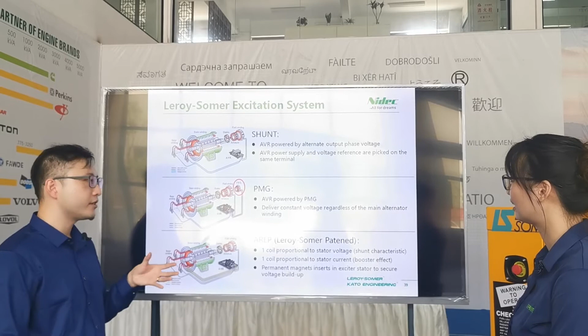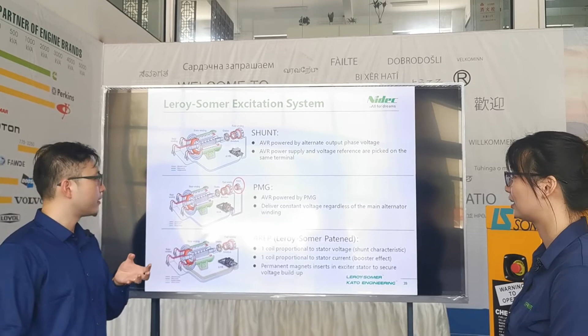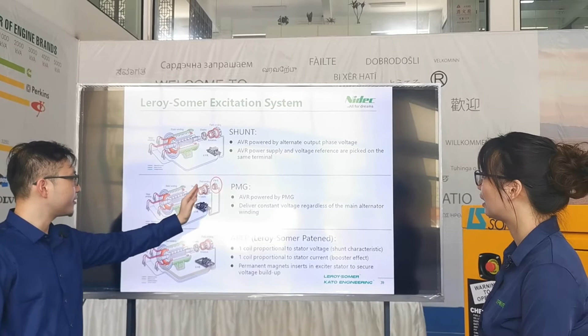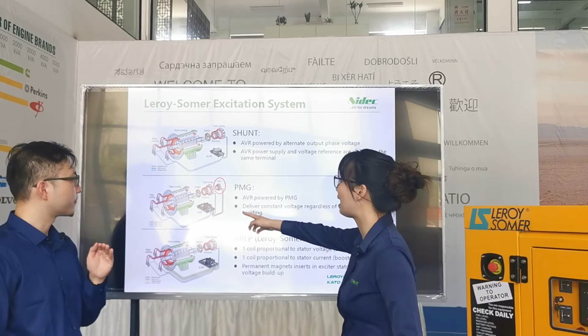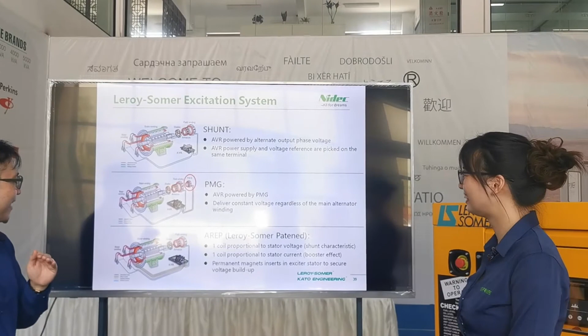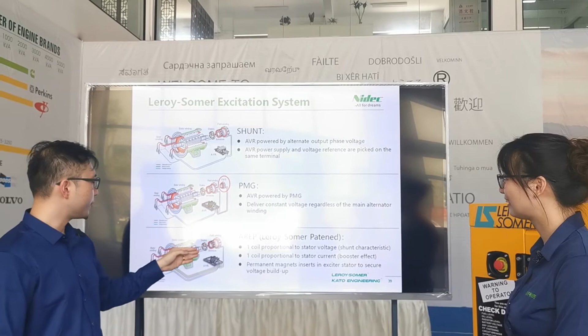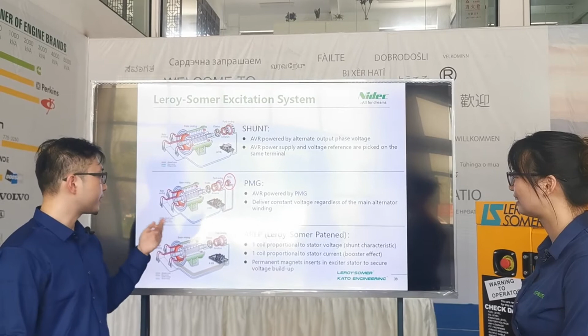The second part is that the PMG, no matter how big or small it is, is a rotating machine. From a mechanical point of view, an additional rotating part will bring additional failure rate - yeah, it's a moving part, so it's more easy to get broken. Without these additional parts, AREP's failure rate will be much better than PMG's. That's the second part.